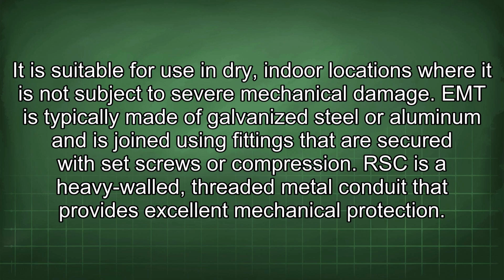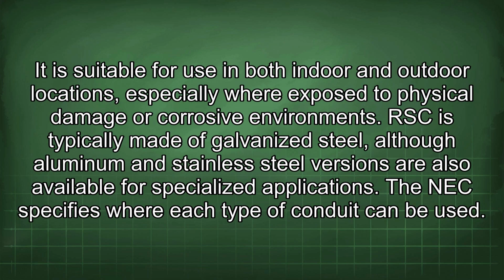or compression. RSC is a heavy-walled, threaded metal conduit that provides excellent mechanical protection. It is suitable for use in both indoor and outdoor locations, especially where exposed to physical damage or corrosive environments. RSC is typically made of galvanized steel, although aluminum and stainless steel versions are also available for specialized applications.